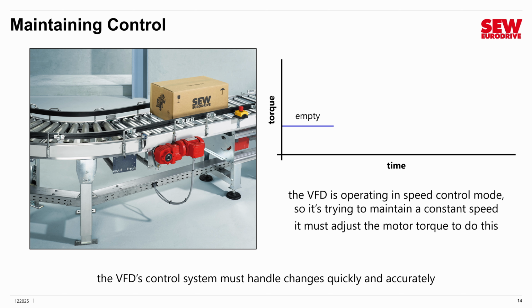We drop a box on the conveyor. That adds a load to the conveyor that wasn't there a second ago. Obviously, more torque must go into that conveyor to keep it running at the same speed or it's going to slow down. What the VFD would have to do is detect the change and increase the torque.